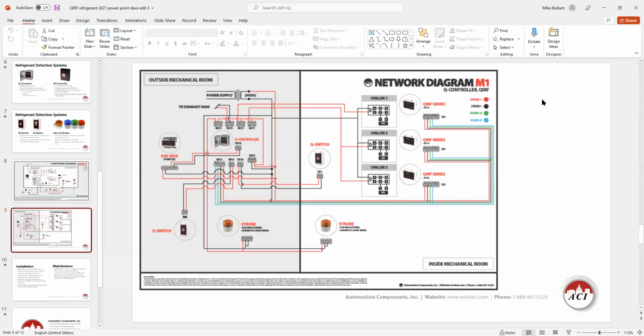So here would be just the same scenario. Let's say this shows three sensors on QIRFs coming back to a Q controller. The reason we did that was because this particular company needed to have BACnet IP back to their BAS. So we have to have the Q controller with the BACnet card in it. And now we use the Q switches instead of the M switches, because it's for the Q controller, it's just wired differently. And then a strobe inside and a strobe outside. So basically the same concept, just a different controller and a different way of communicating back.